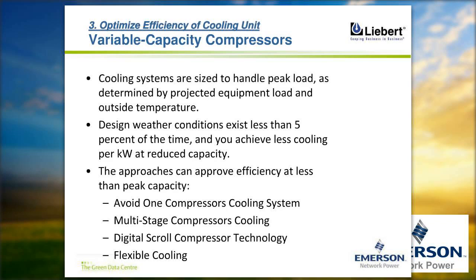Okay, variable capacity system. Data center loads are very dynamic. They are different every day. The ramp up times are also very different. On weekends they are different, on month end they are different. And every time the heat rejection required is going to be different because servers, storages and all other devices are going to work on a different loading factor. And with that, if you can build an intelligent cooling system which will modulate with respect to the cooling or heat rejection requirement, then you can save further electrical consumption. So here we recommend customers to use variable compression or variable capacity.